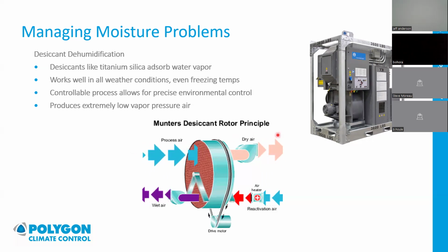If you're measuring it in relative humidity, it's going to be less than 10% RH, is kind of the rule of thumb. Now, eventually this wheel would be totally full of water because that silica can only grab so much water vapor, and then it would be useless, right? You'd just be pushing air through a wet wheel and the wheel wouldn't grab any more water. So to reactivate that wheel, there's a heater.